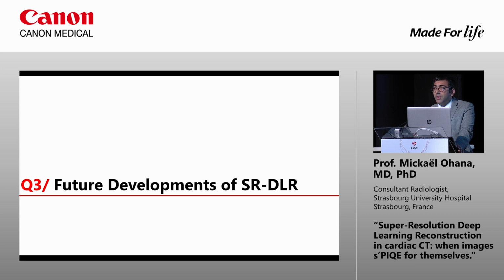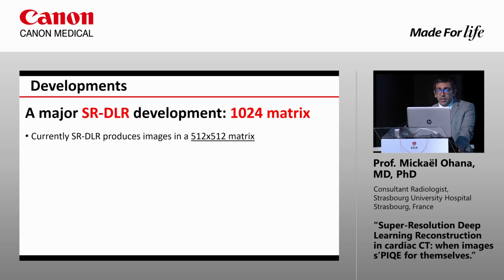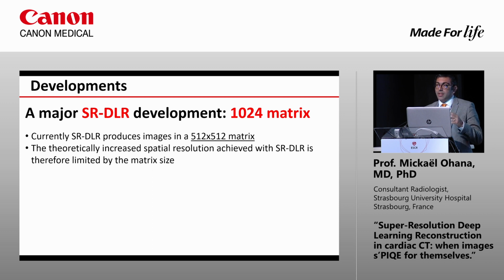So what are the future developments of this technology? A major development that is currently under study is the usage of a 1024 matrix. Currently, when you use SR-DLR, the end result is in a 512 by 512 matrix. So theoretically, the increased spatial resolution that you can achieve with SR-DLR is limited by this matrix size.